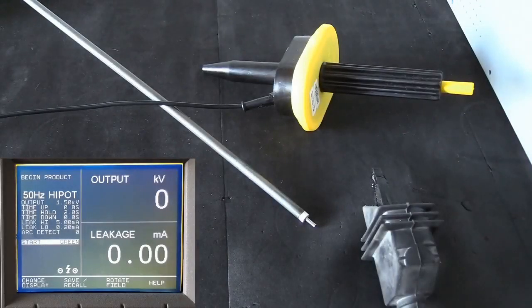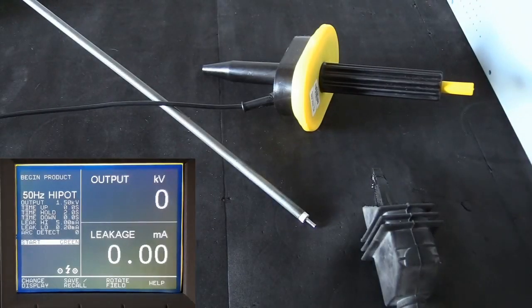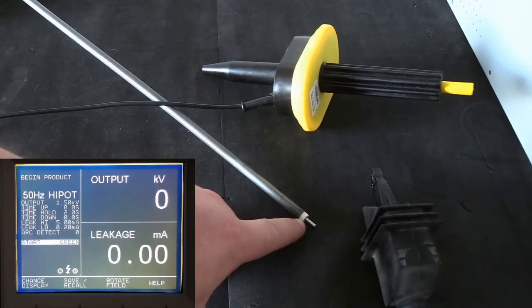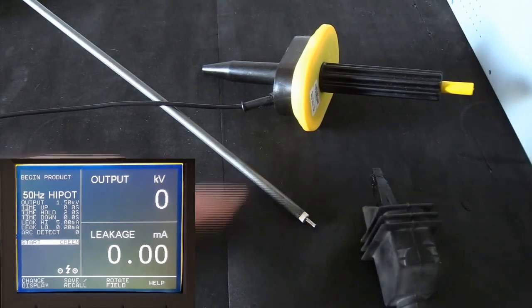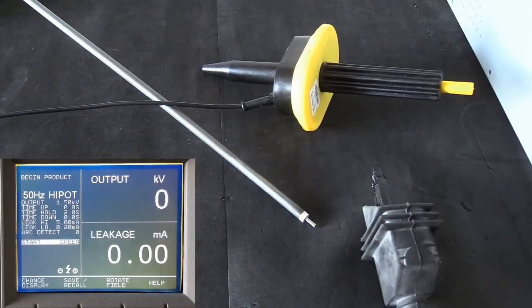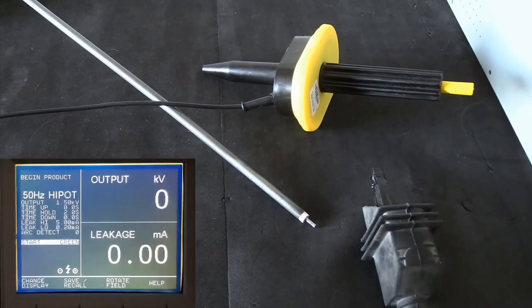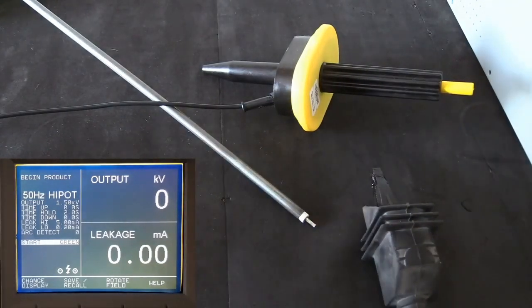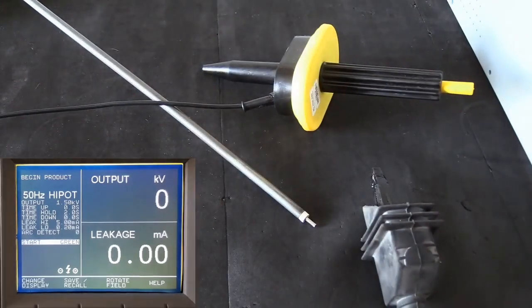In this first demonstration, we're going to test a simple resistive heating element. Now, the element itself comprises 3 main parts. There's the internal resistive core, there's an insulation level barrier, and then there's also the external metal. And you'll see that internal insulation and then the external metal sheath. So we're going to be testing the strength of the insulation between the resistive core and the metal sheath externally.